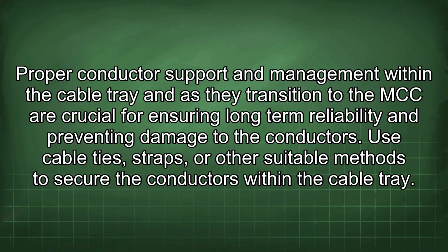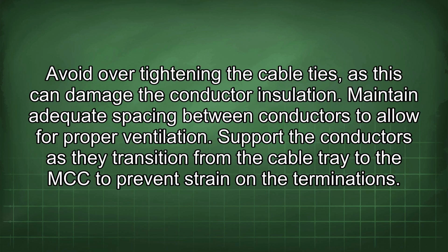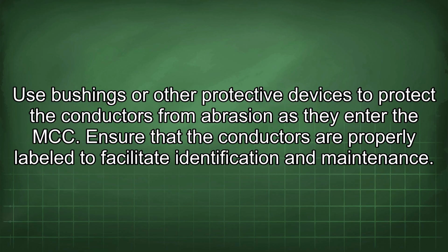Proper conductor support and management within the cable tray and as they transition to the MCC are crucial for ensuring long-term reliability and preventing damage to the conductors. Use cable ties, straps, or other suitable methods to secure the conductors within the cable tray. Avoid over-tightening the cable ties, as this can damage the conductor insulation. Maintain adequate spacing between conductors to allow for proper ventilation. Support the conductors as they transition from the cable tray to the MCC to prevent strain on the terminations. Use bushings or other protective devices to protect the conductors from abrasion as they enter the MCC. Ensure that the conductors are properly labeled to facilitate identification and maintenance.